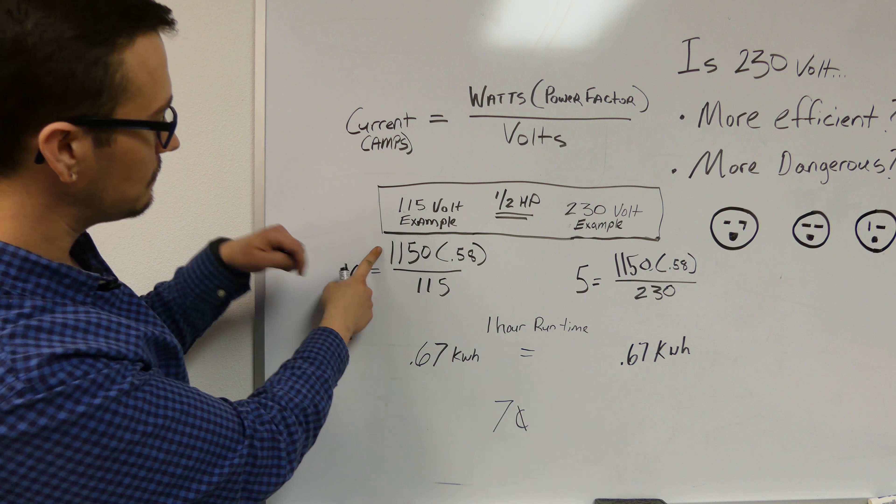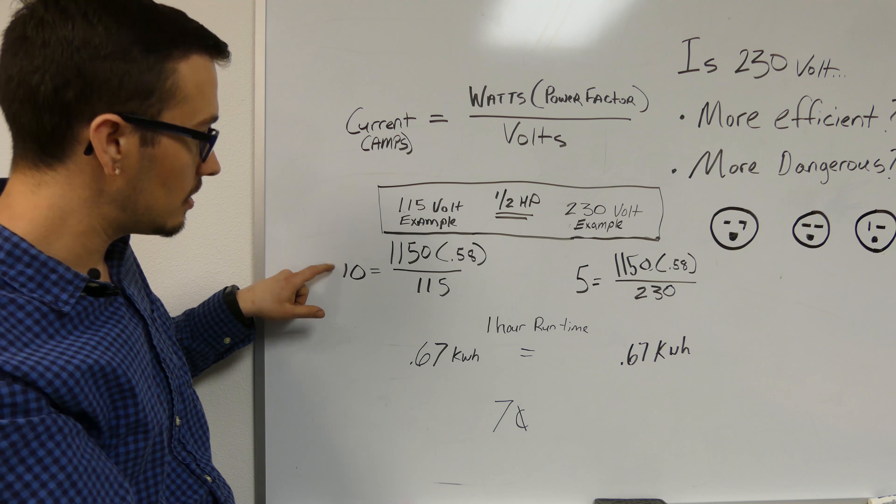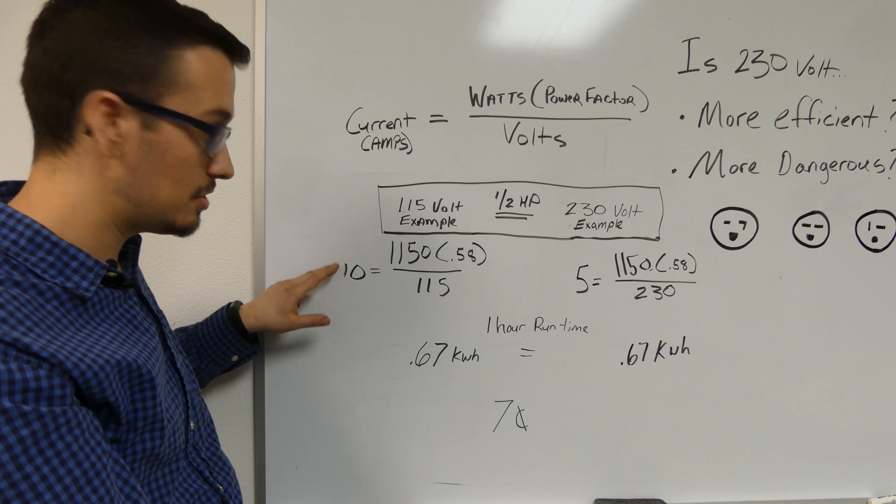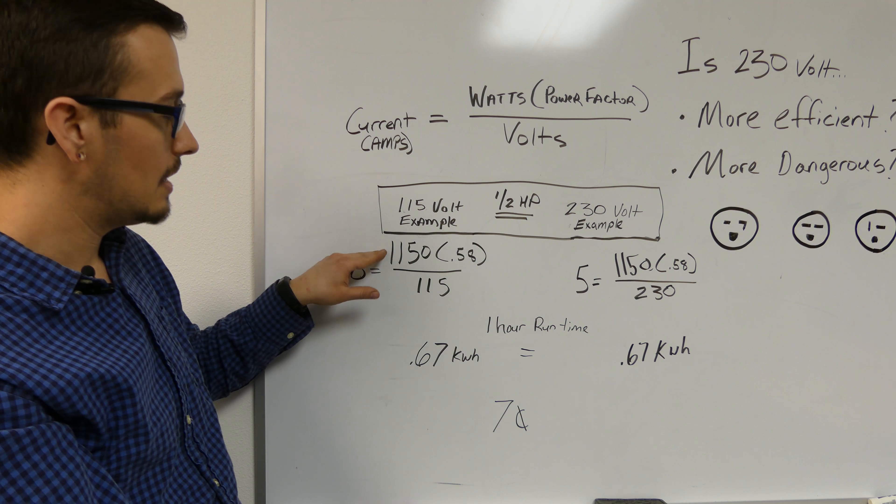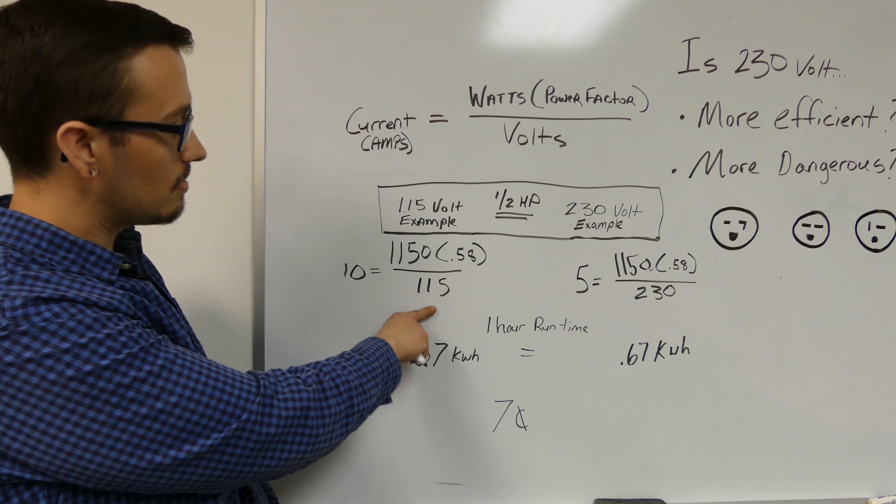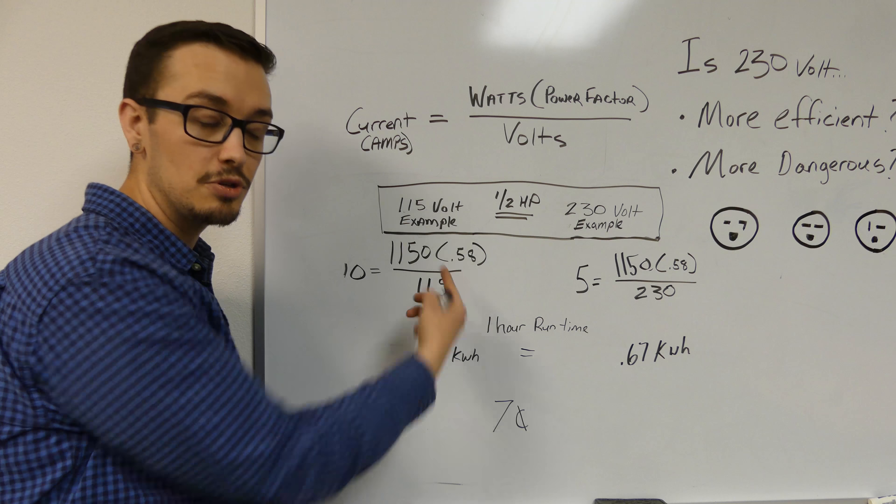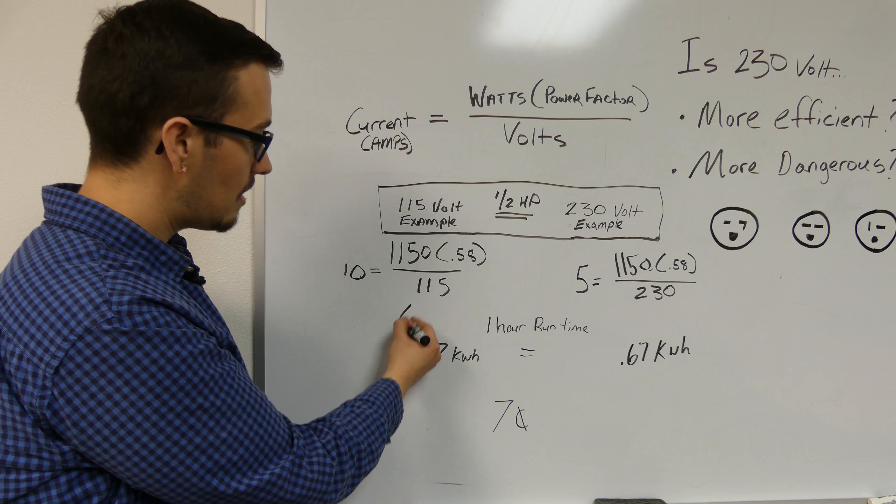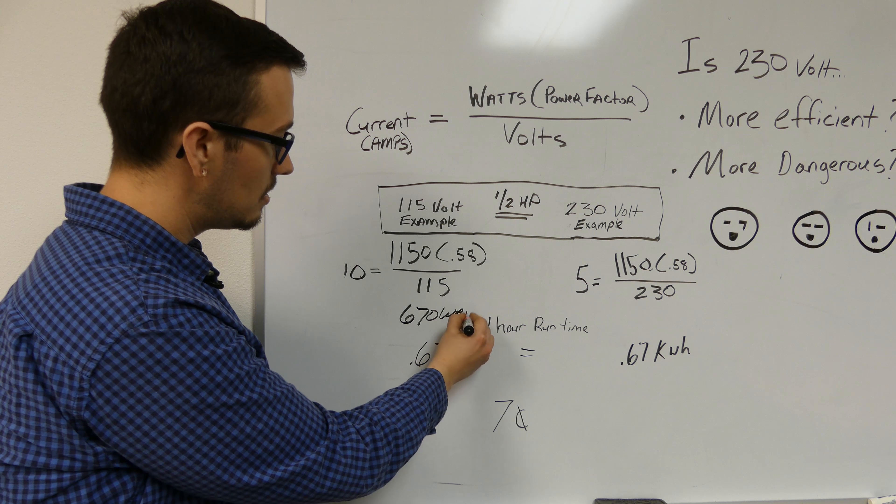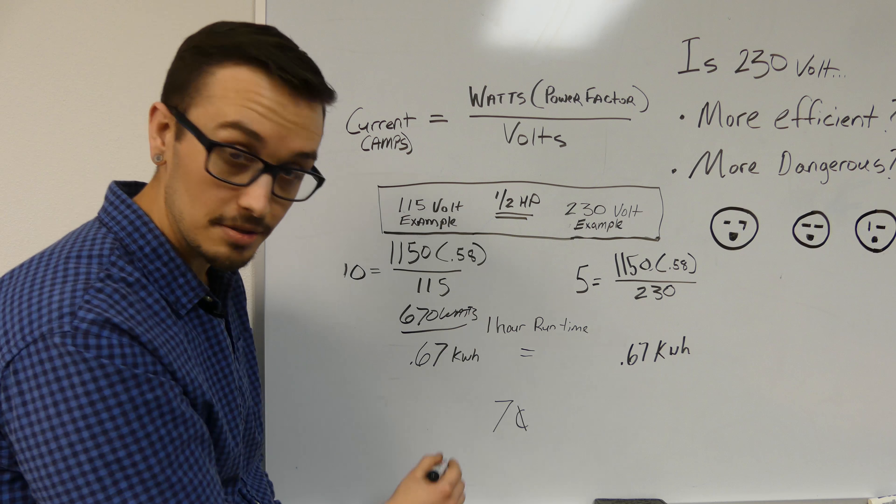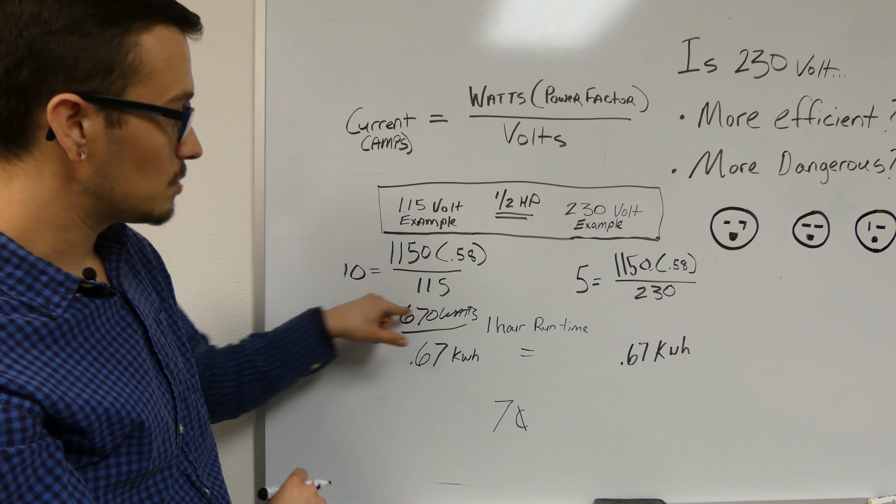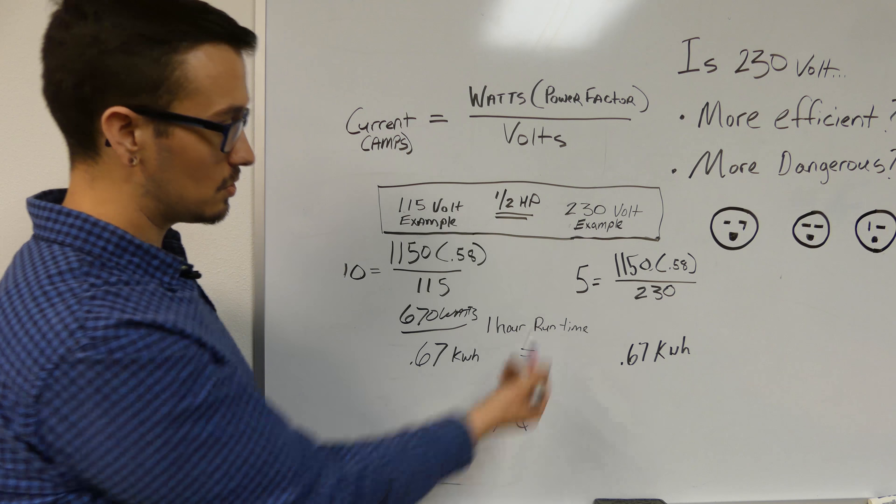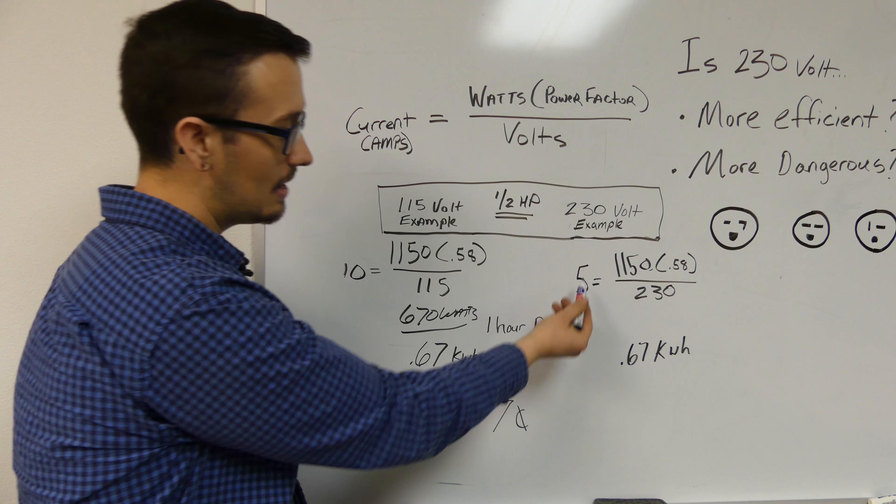We've got a 115 volt example here with half horsepower motor information shown. If we take 10 times 115, we get 1150. The motor is 10 amps on a half horsepower based on the pump manufacturer's nameplate information. We multiply 1150 by the power factor, which is also information on the motor, and we end up with about 670 watts.